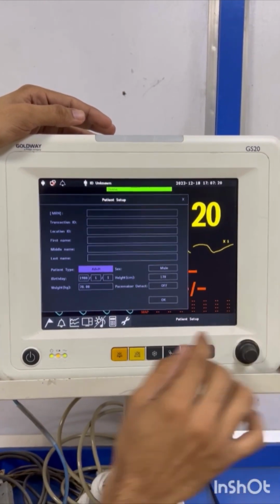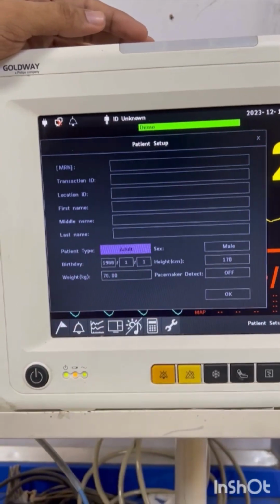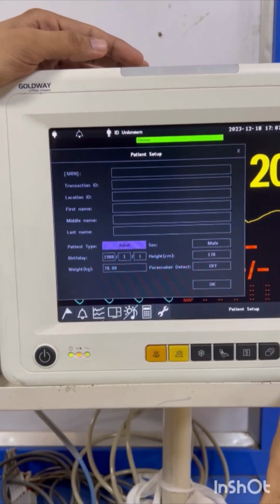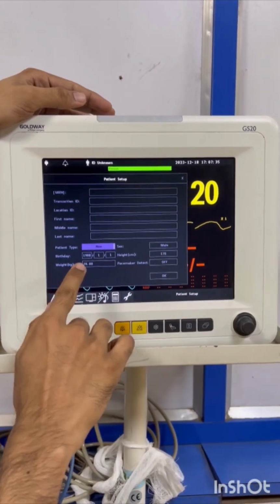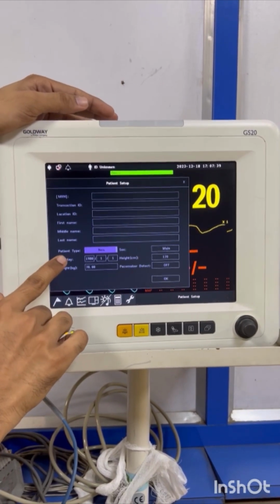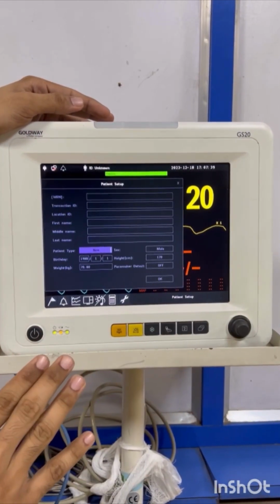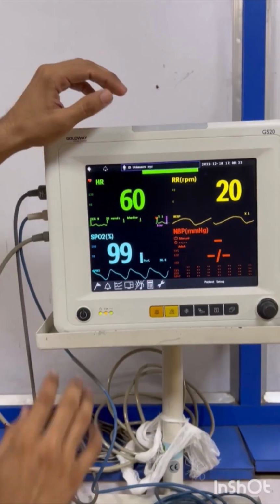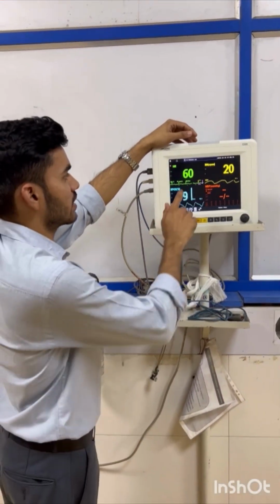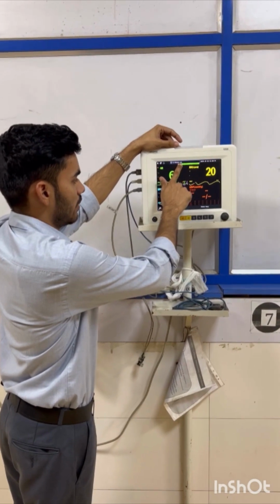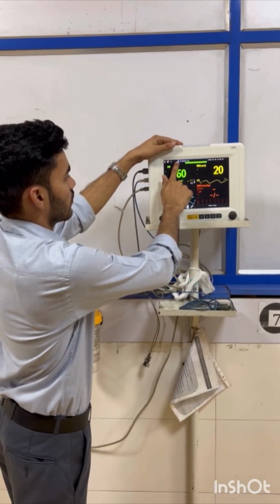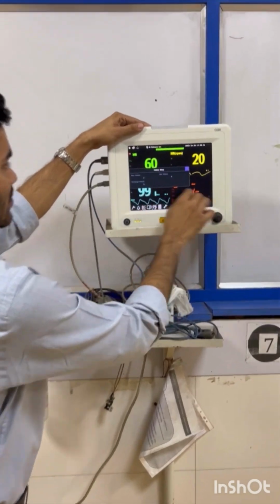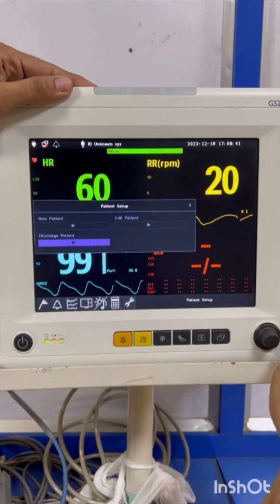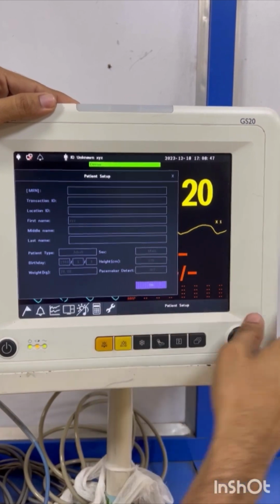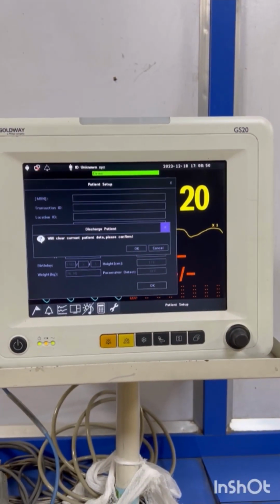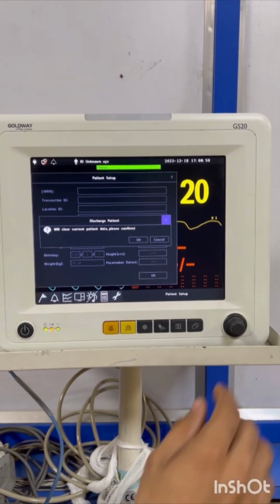The important parameter is patient type. Make sure you are properly selecting the patient type, that is adult, pediatric or neonate. According to patient type you are selecting over here, all the alarm limits will automatically get adjusted. So now the name I have inserted, it is shown over here, patient name. Whenever you are going to discharge the patient, you will again come to this menu. You just have to select discharge patient and you have to press OK. So whenever you discharge a patient, all old data of patient will get erased.